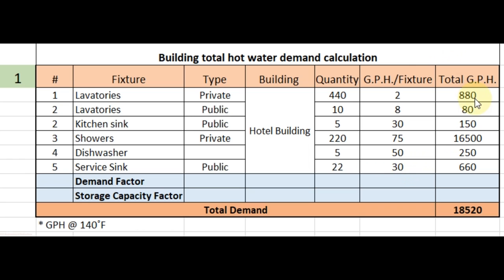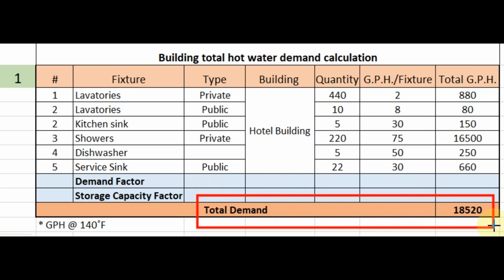Now we get the results. Total hot water demand: washbasin private — 880 GPH; washbasin public — 80 GPH; kitchen sink — 150 GPH; shower — 16,500 GPH; dishwasher — 250 GPH; service sink — 660 GPH. The total hot water demand for the complete building is 18,520 gallons per hour.